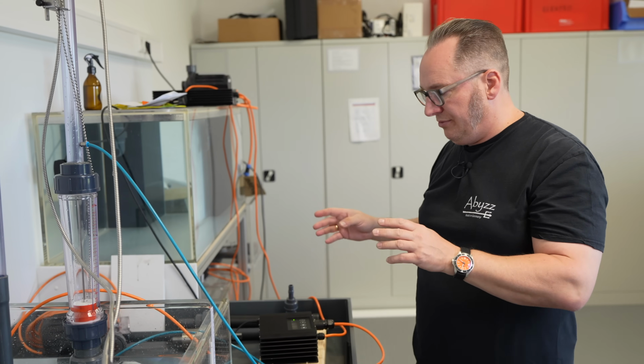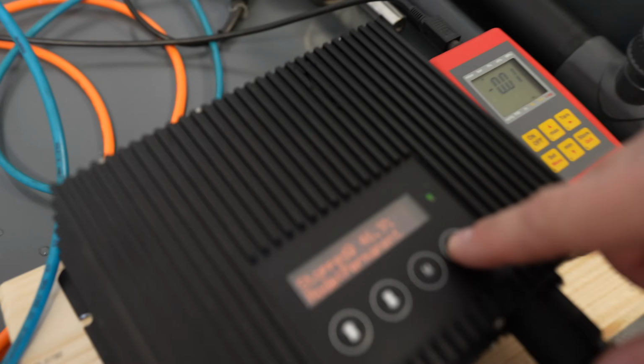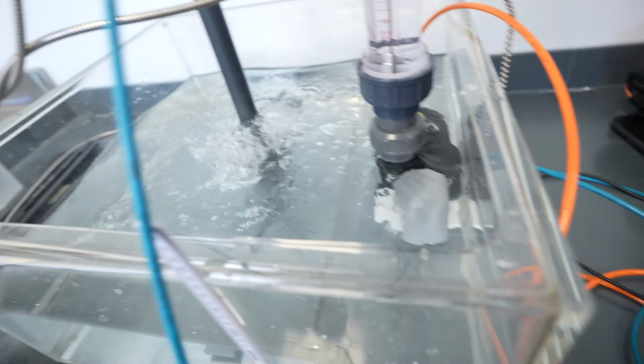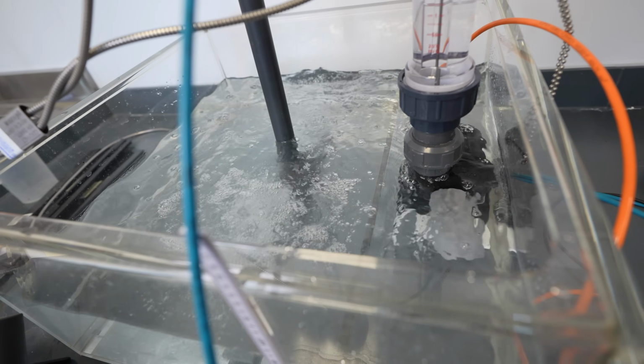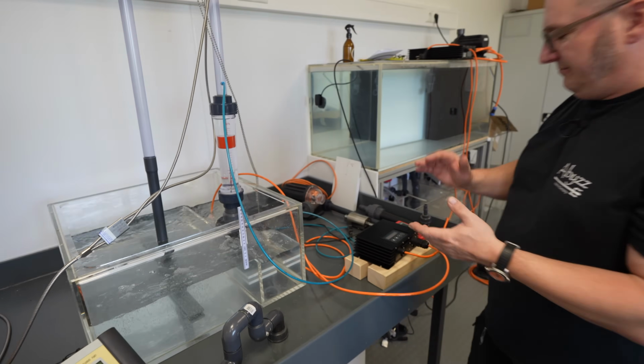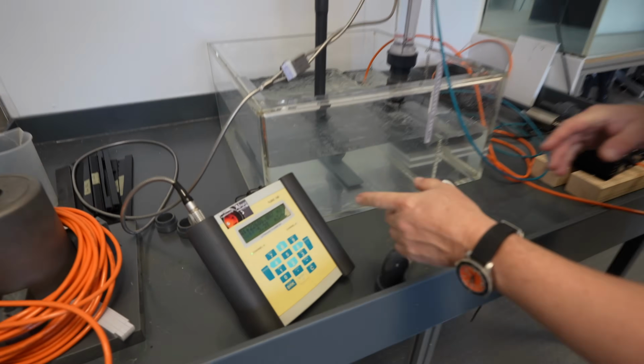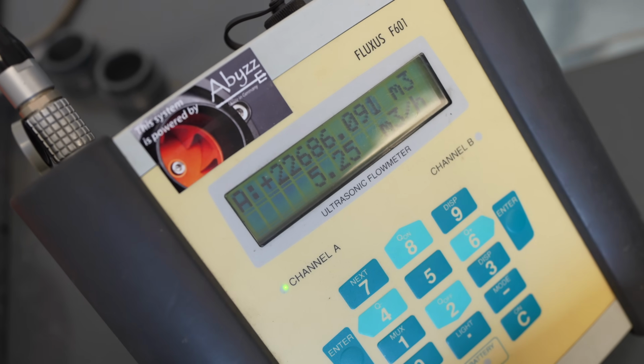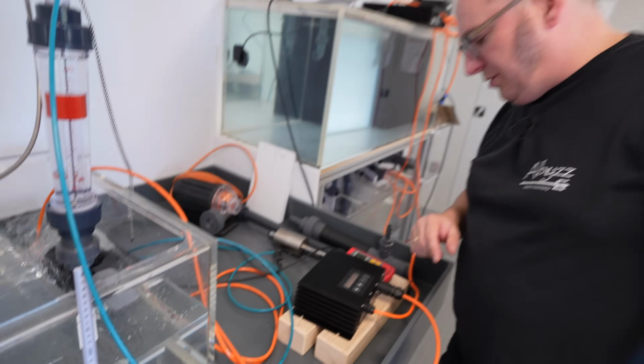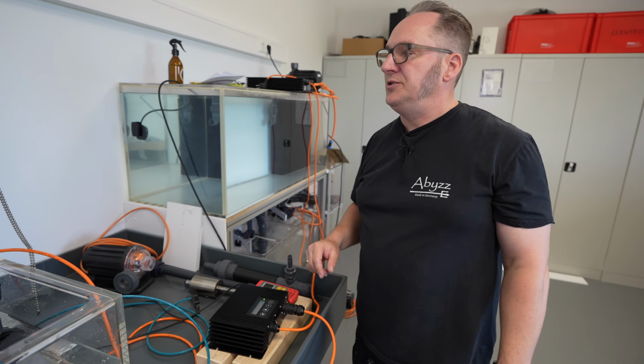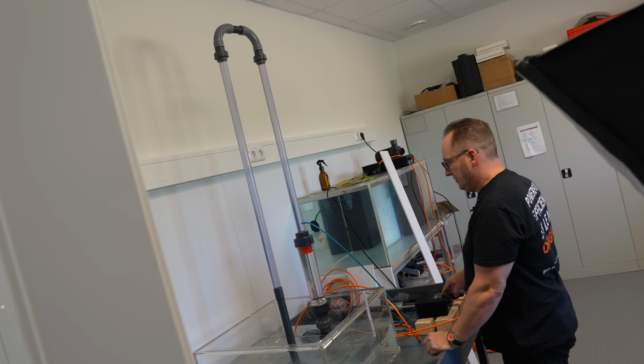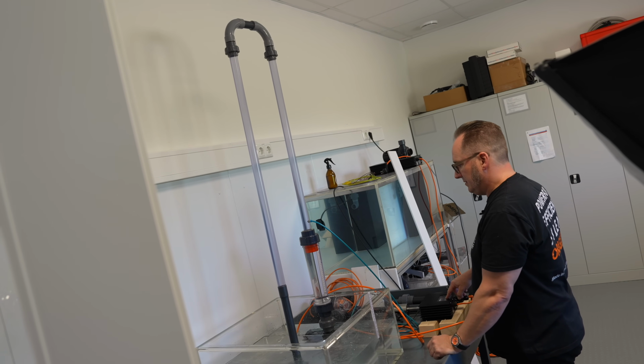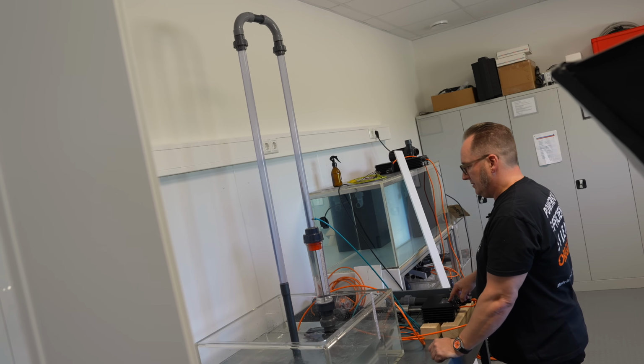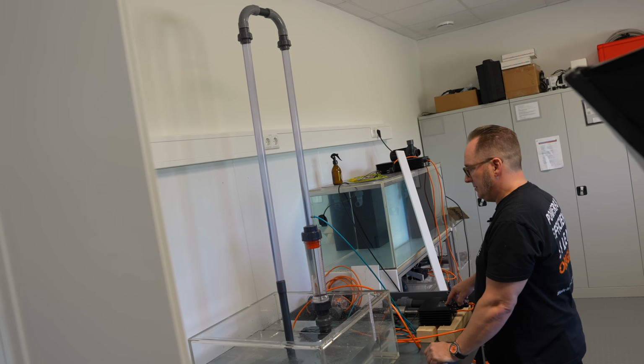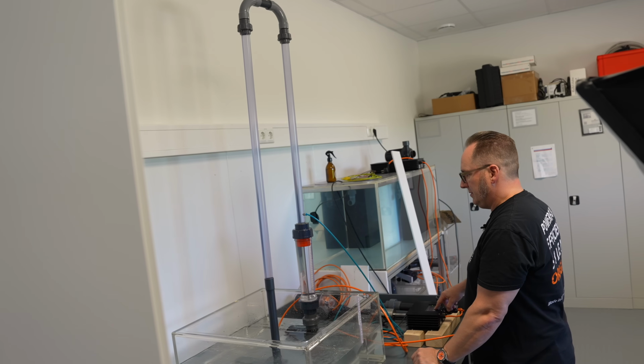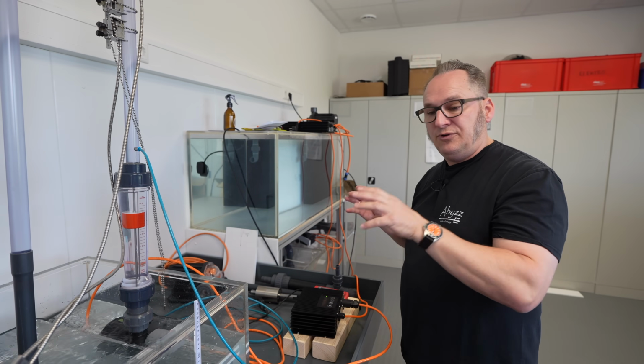I've set the whole thing up already to run at 46.9%, which should give us a nice flow rate of roughly 5 cubic meters. All right, that worked obviously. So there's 5.2 roughly, and here we have 49 watts with 46.9%. This is the flow rate that the design is actually made for. We are running this with 32 millimeter acrylic pipe with a wall thickness of roughly 2.2 millimeters. We are exactly at that spot right now where the plumbing would be the right size for 5 cubic meters.